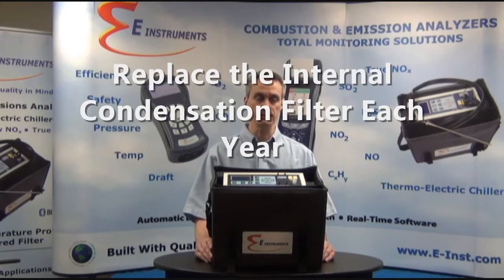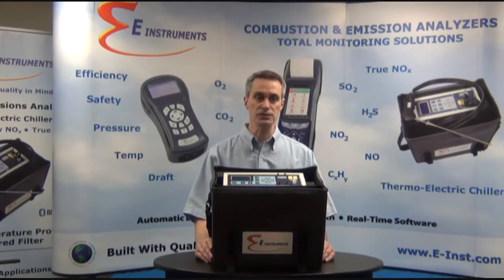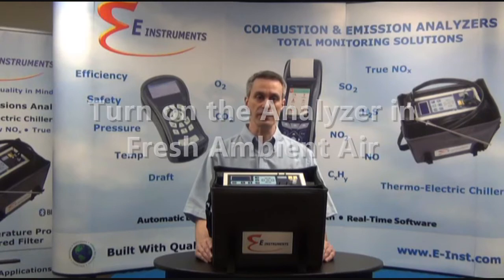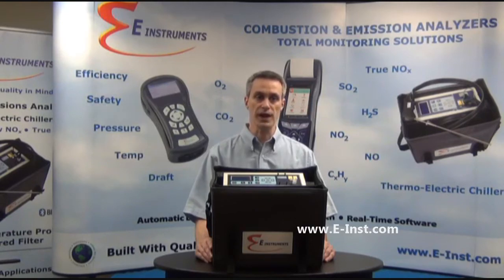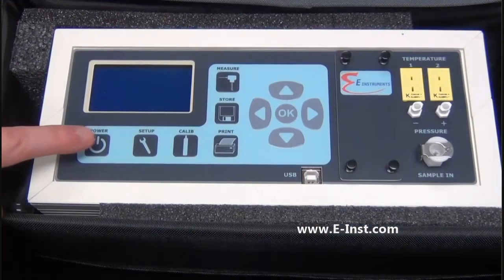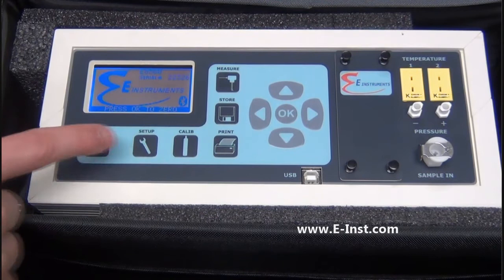It is recommended to replace this filter once each year. You need to open up the analyzer by removing 4 screws to access and replace the condensation filter. It is recommended that the unit is turned on in a fresh ambient air environment since the analyzer runs an auto calibration cycle right after the analyzer is turned on. Turn on the analyzer by holding down the on-off button.